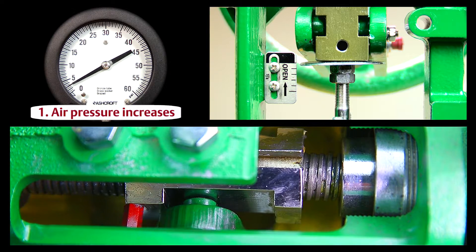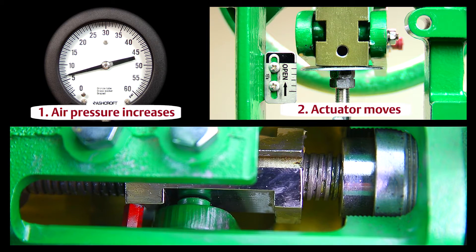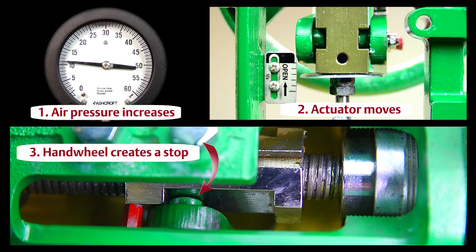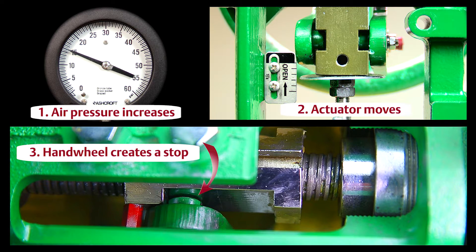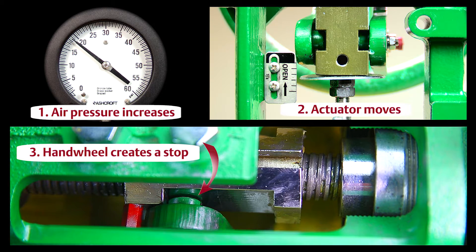Leaving the handwheel engaged in any position other than neutral will create an adjustable stop that prevents the valve from fully opening or fully closing.